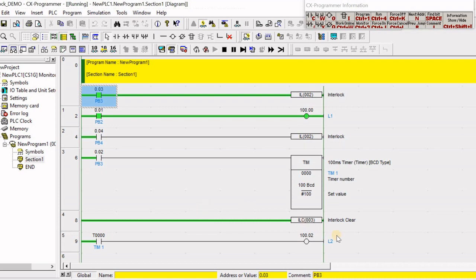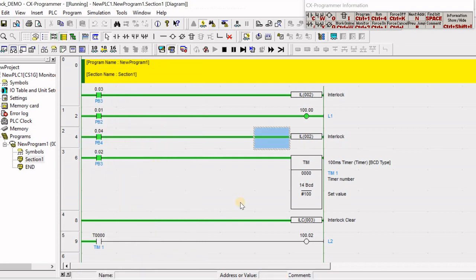Say for example you wanted to just execute the timer. You want to forget everything else. But the problem with interlock is that you cannot disable things outside the gate. So if you, for example, disable the outer ones, even both the inner ones, the programs between the outer interlock will also be deactivated.